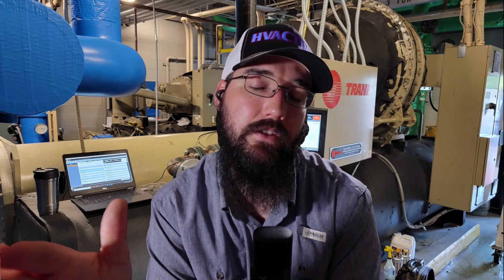A new TXV where everything's properly done may be silent, and you may not even be able to feel it, but it will likely be silent throughout its in-between travel. You'll only hear it bottom out and top out, and that's it. And even the bottoming and topping out might be fairly quiet. Not always, so it just kind of depends. But if you can hear that same ticking noise during the travel between top and bottom, that valve, if it hasn't fully failed yet, is probably not that far from it. So these are things to be aware of and pay attention to in this process, making sure that we're listening and monitoring through our sight glass and that we are getting a proper calibration.